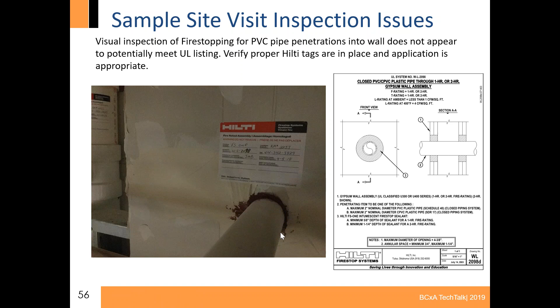And the reason for this, if you think about it, when you get to the larger PVC pipes, you have that intumescent fire caulk that expands, right? But if it's too large of a space, it can't expand to fill that whole space. So it's really important to use the right system. That fire caulk they specified to fill in the wall at 5/8 inch could do up to a 2-inch PVC pipe. When you get bigger, they have different systems available.